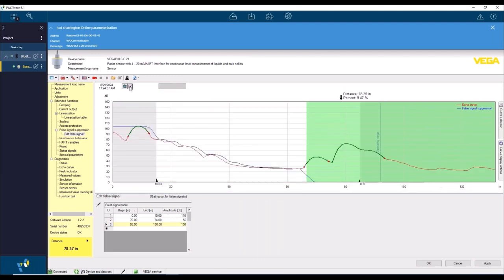Now next, the final one down here, what we're going to do is figure out where we're starting. This is much easier. For that last and final edit, you take your distance B value. So whatever distance B is, you add 10 inches to it and make that the beginning of your manual edit. So my distance B is 85 inches. I'm adding 10 inches, as you can see here, to make it 95. And then you take it completely off the scale. You can put in 150, you can put in 200, but just take it off the scale and make the amplitude 100, and then hit apply.